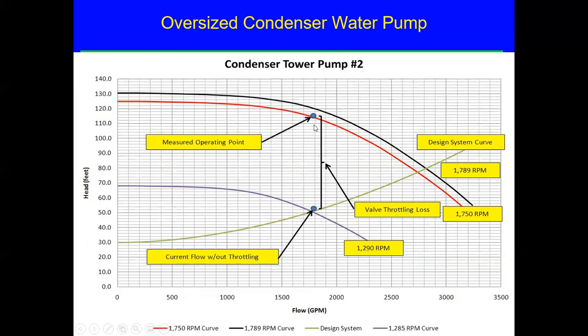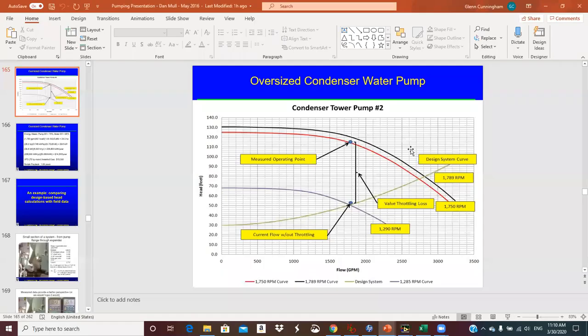And this is with throttled valves, or control valves. And we see that if we were to open the valve and slow the pump down, and these curves shifted a little bit in copying, but if we could slow the pump from, say, 1750, 1780, whatever RPM, down to about 1290 RPM, we could operate down here on the system curve and produce, oh, I don't know, 50-something feet of head, which would be far less pump energy. So that's kind of what the variable speed pumping is all about. And we don't do a whole lot of that in this course. We do quite a bit of it in the 4260 class.